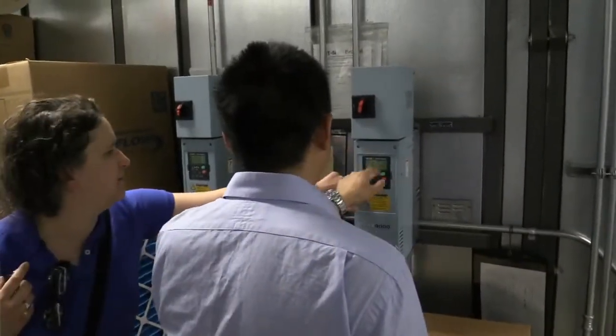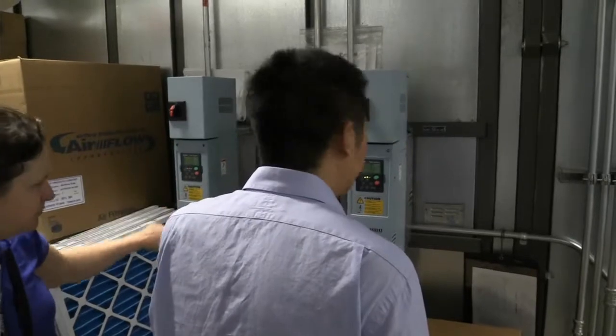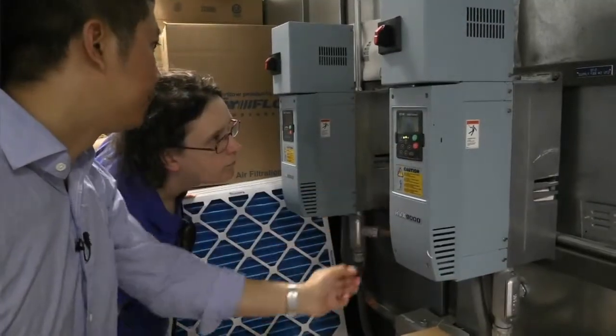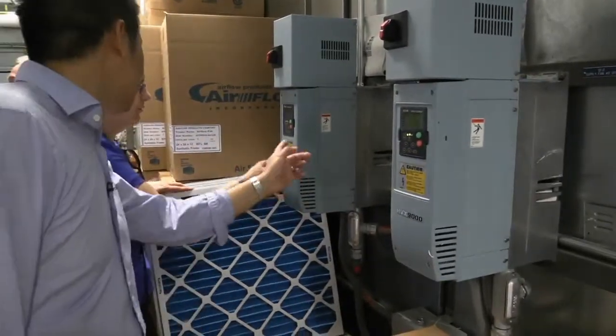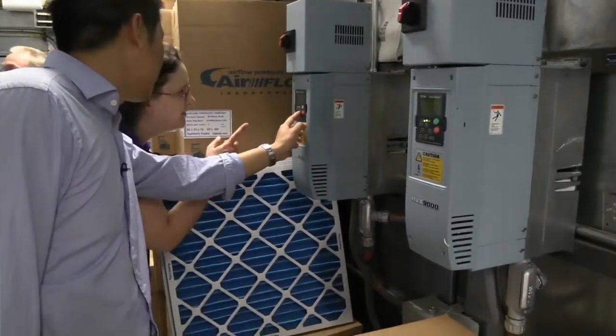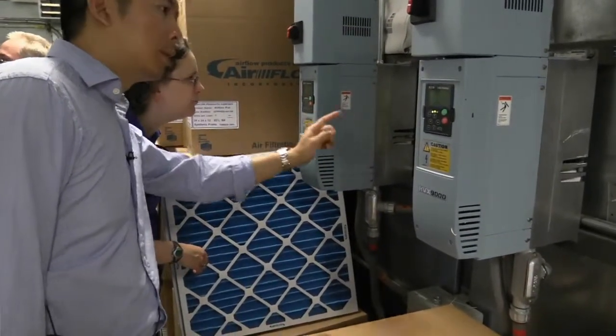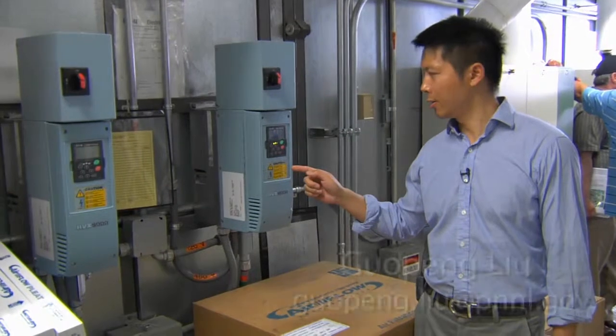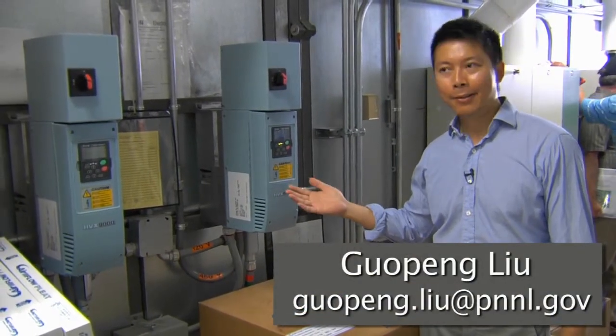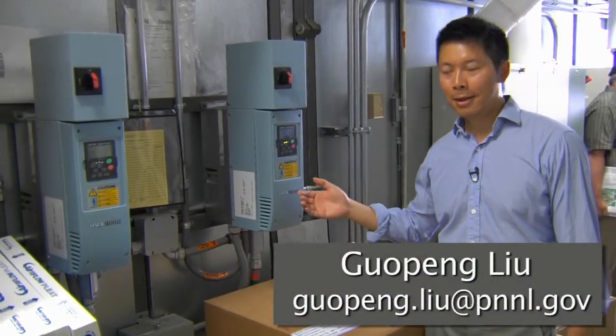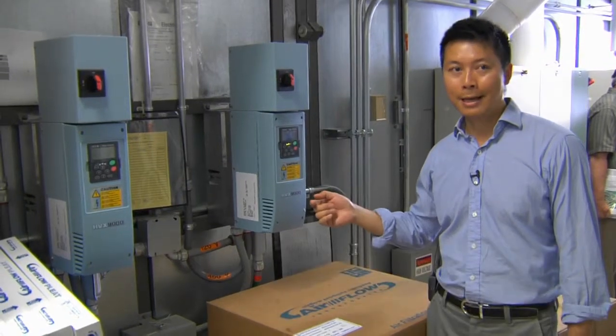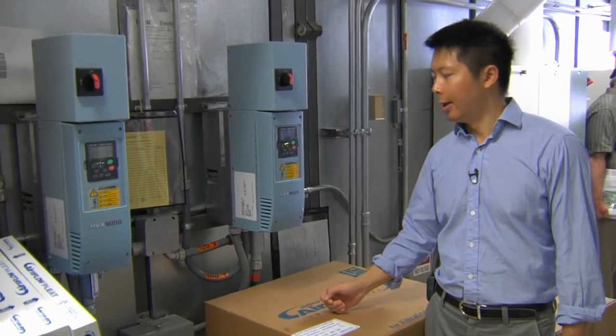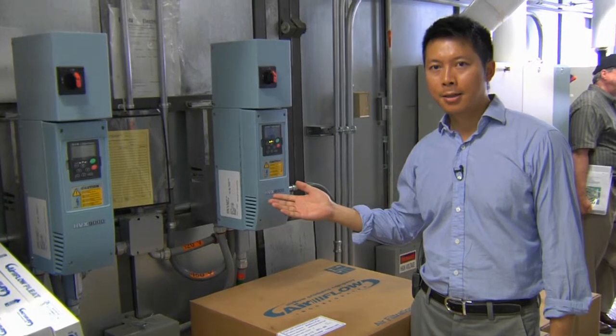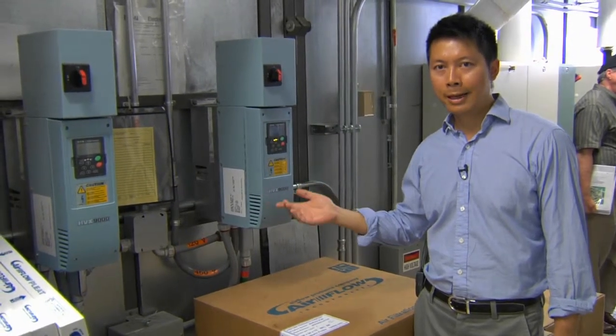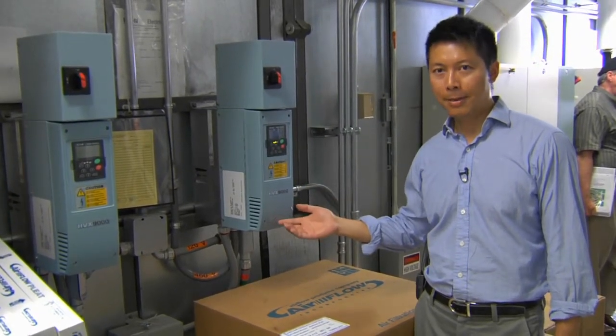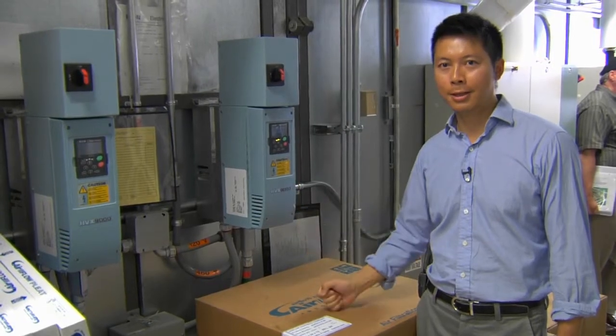These two VFDs are for the supply fan for air handler 17, and you can see the VFD speed ramp up from 34 Hertz to 37 Hertz in a very short time frame. That can be hard on the motor and the belt. It could be related to the static pressure control. So we'll later on look at the control program and figure out what the control logic is for this.